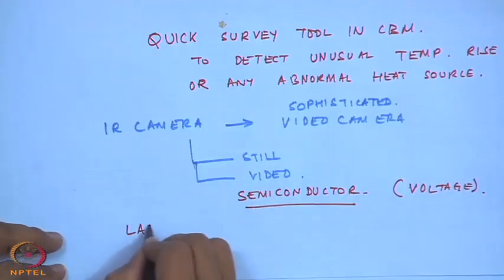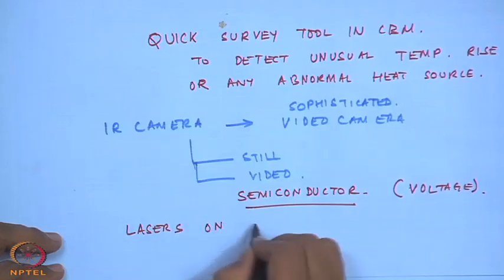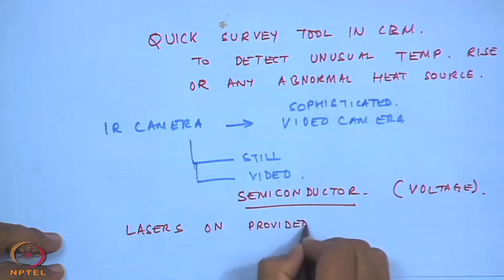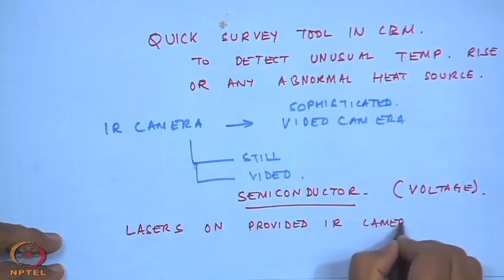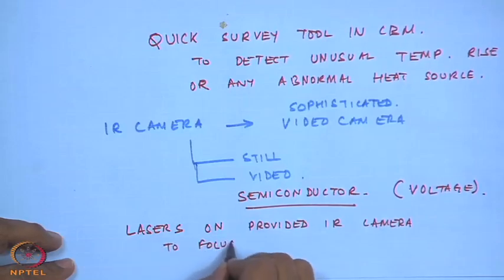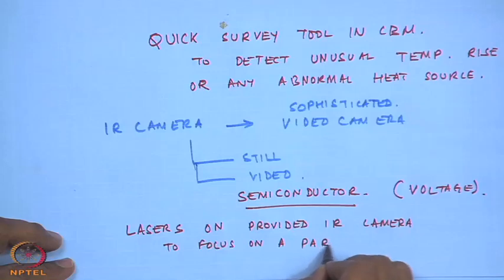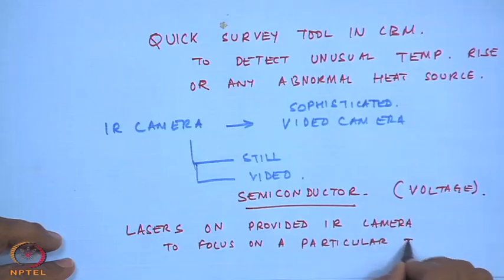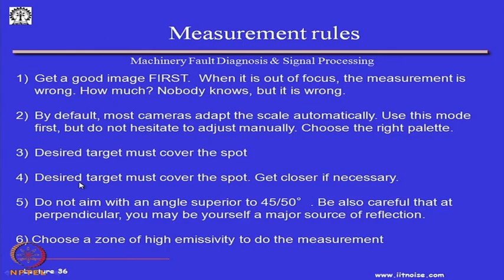Sometimes lasers are provided on such IR cameras to focus on a particular target. The desired target must cover the spot, and that is why sometimes we have to use a laser. And do not aim with an angle greater than 45-50 degrees, but sometimes, you know, if you are perpendicular to the body, you may also be reflecting, so choose a zone of high emissivity to do the measurements.